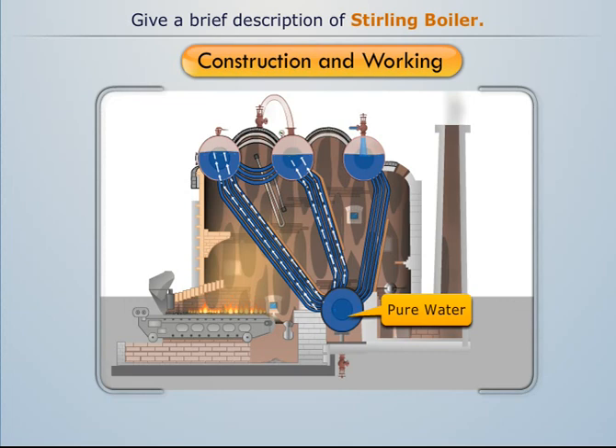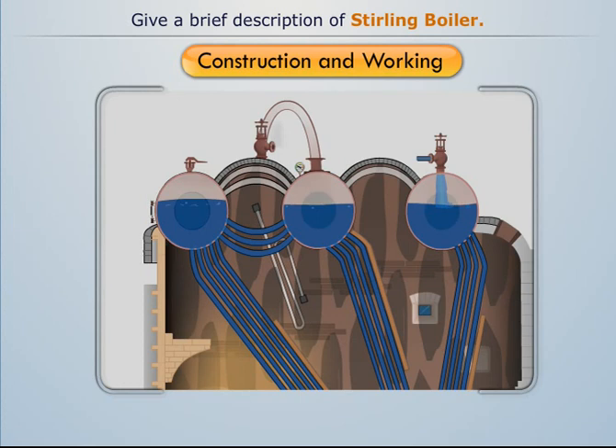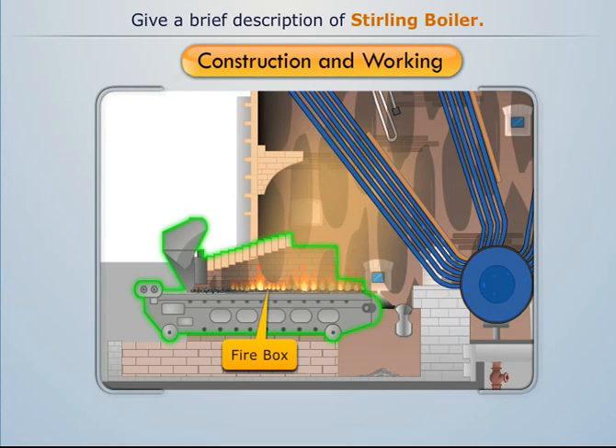The steam drums are also connected with each other by equalizing tubes and circulating tubes. The circulating tubes equalize the level of water in the drums, while the equalizing tubes equalize the level of steam in the drums. The firebox is situated at the bottom left corner of the boiler settings, where solid fuel is burnt over a grate to produce hot flue gases.